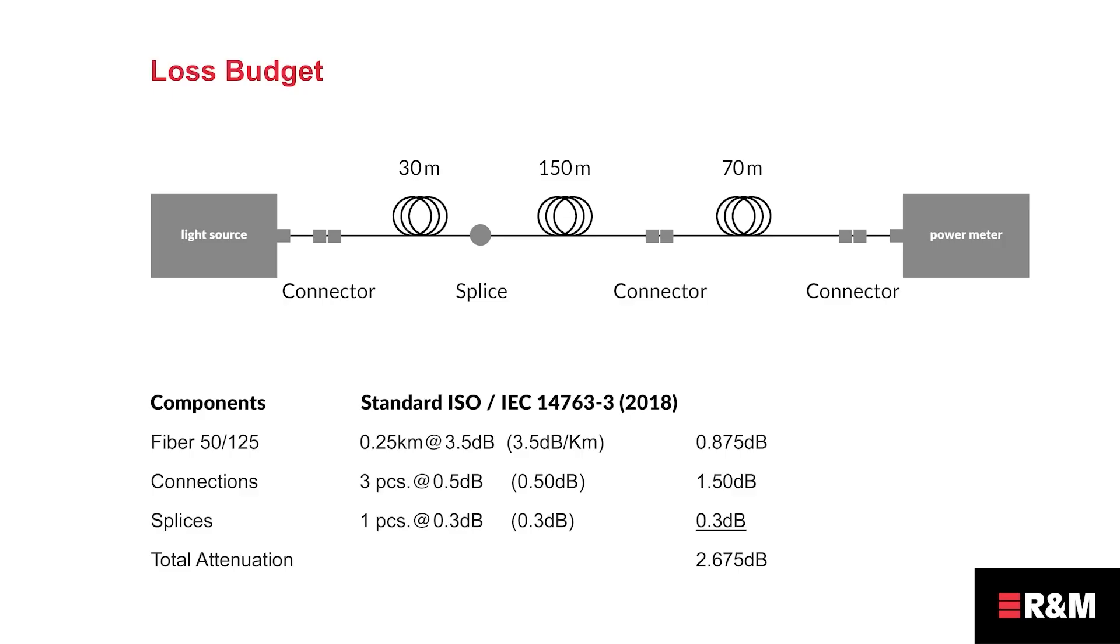The loss budget must be calculated. It is an accumulation of all components within the specific link. This means that all connectors, splices and the entire cable length are included. The specific loss values of the components are added together to give the maximum overall loss. This example shows the values of the standard ISO IEC 14763-3.